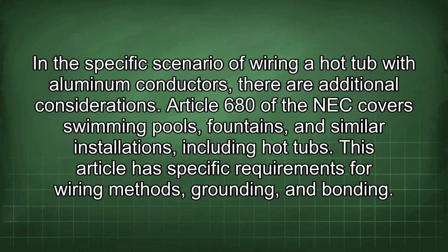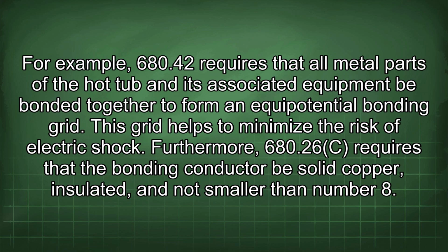In the specific scenario of wiring a hot tub with aluminum conductors, there are additional considerations. Article 680 of the NEC covers swimming pools, fountains, and similar installations, including hot tubs. This article has specific requirements for wiring methods, grounding, and bonding. For example, 680.42 requires that all metal parts of the hot tub and its associated equipment be bonded together to form an equipotential bonding grid. This grid helps to minimize the risk of electric shock. Furthermore, 680.26(C) requires that the bonding conductor be solid copper, insulated, and not smaller than number 8.